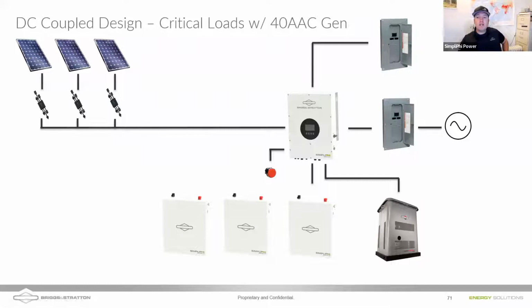This is an example of what it looks like with our new inverter. Again, a DC coupled system. The batteries are our internal SimpliPhi batteries, the 4.98s. Non-backed up loads here, I'm sorry, and backed up loads up here. Here's grid. In this example, I want to demonstrate how generators can integrate into energy storage systems. Internal to our new inverter is, like I mentioned, 2-wire generator start. So if those batteries start to get depleted, there's no sun, it's cloudy or nighttime, we can send a 2-wire signal to start up that generator, charge those batteries up, and then shut the generator off.